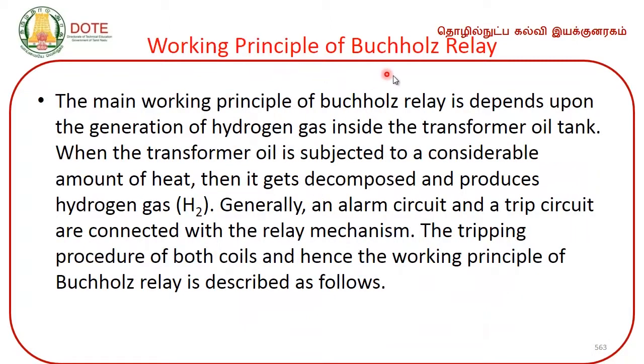Working principle of Buchholz relay. The main working principle of Buchholz relay depends upon the generation of hydrogen gas inside the transformer oil tank. When the transformer oil is subjected to a considerable amount of heat, then it gets decomposed and produces hydrogen gas, H2. Generally, an alarm circuit and a trip circuit are connected with the relay mechanism. The tripping procedure of both the coils, and hence the working principle of Buchholz relay, is described as follows.